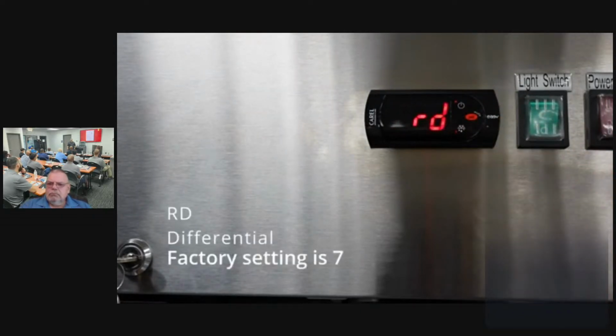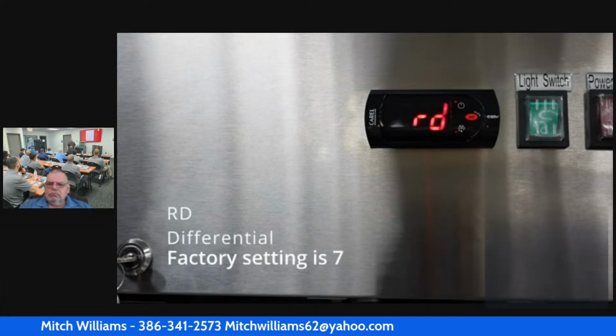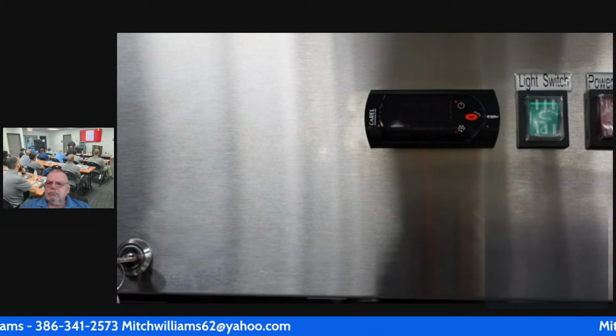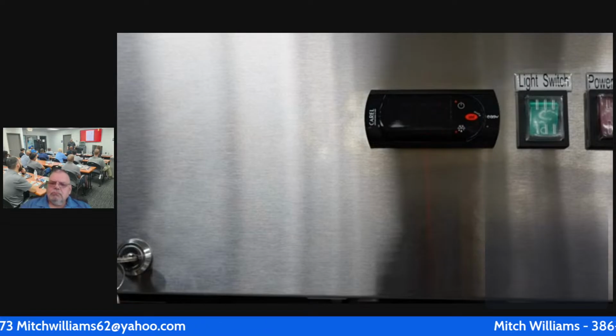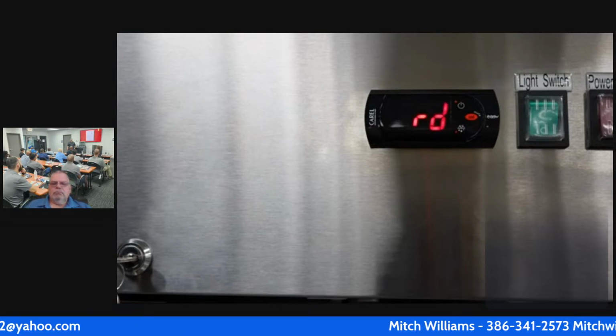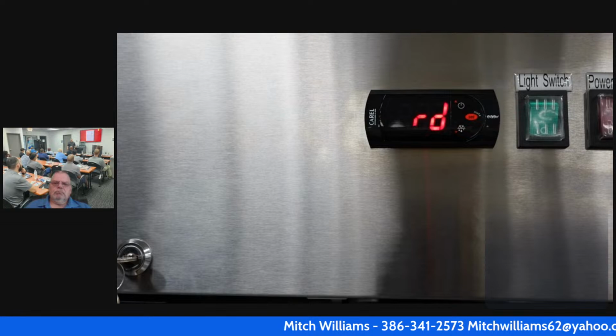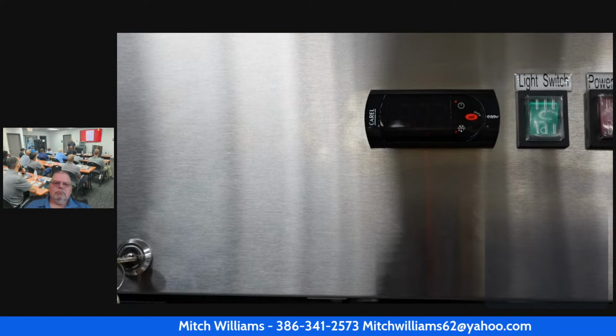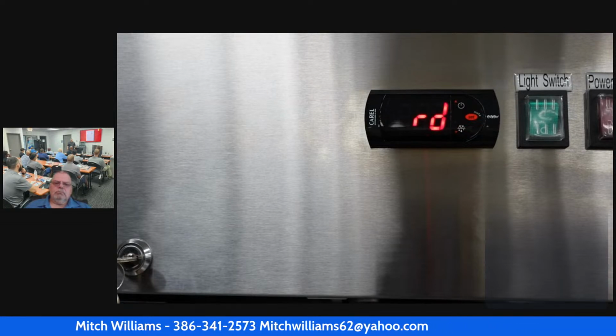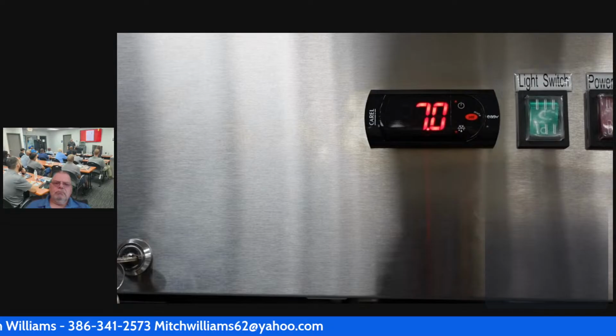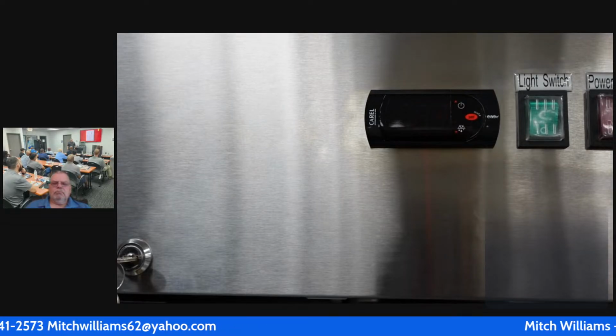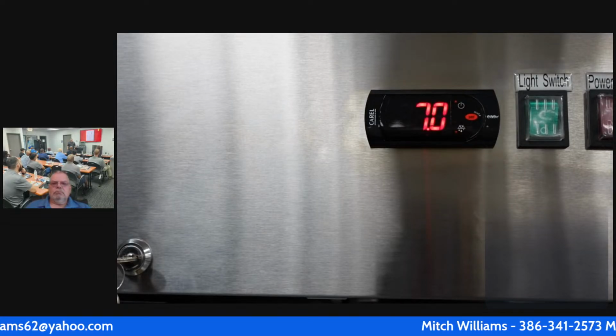The next one we'll see is RD. RD is the differential. The differential is the temperature swing in the unit, meaning if the unit is set to 37 degrees, the compressor will not come back on until the display reaches 44 degrees. The factory setting is 7. You could adjust this parameter lower, but that will result in the unit cycling more.